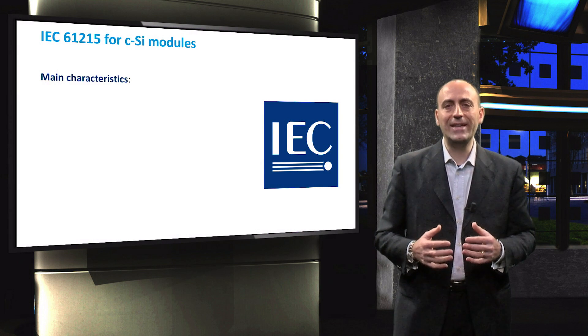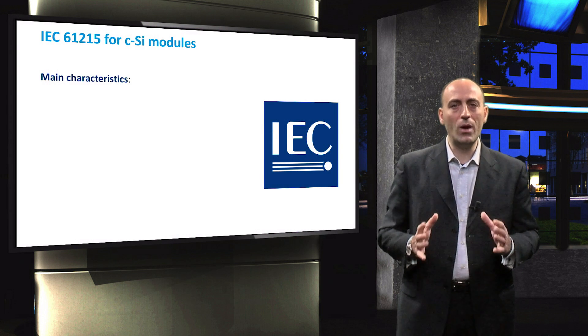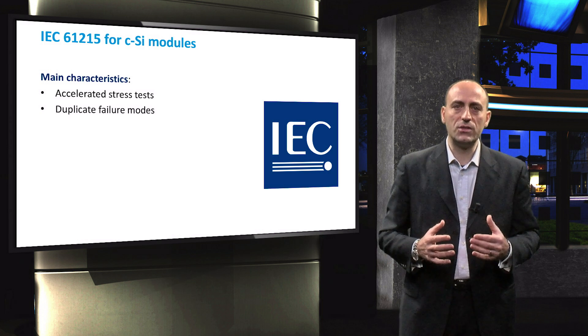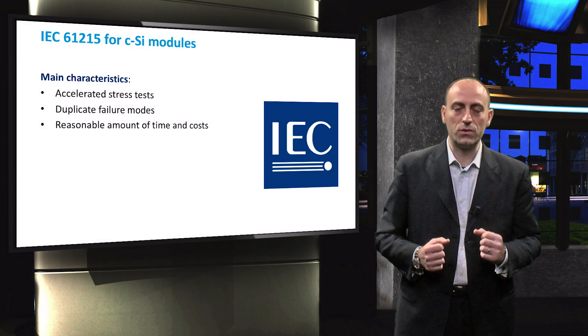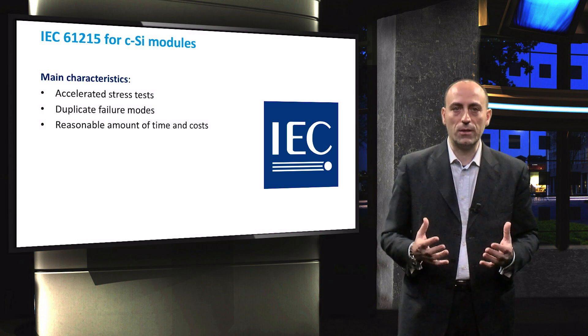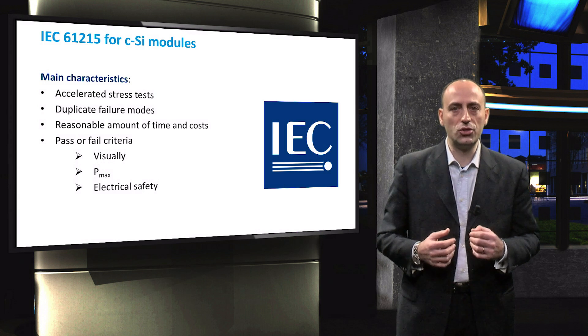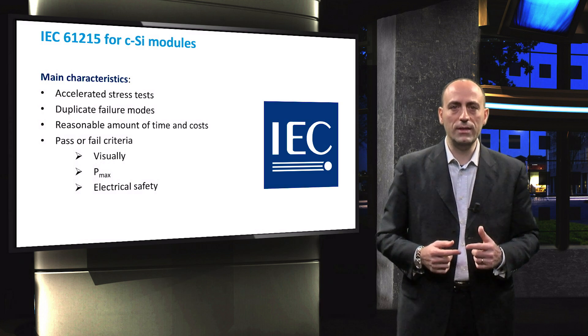Let us now focus on the IEC 61215, which is applicable to crystalline silicon modules. The qualification includes a set of well-defined accelerated stress tests that aim to duplicate failure modes observed in the field. It is important that stress levels and test durations are limited so that the tests can be completed within a reasonable amount of time and cost. The IEC 61215 prescribes a sequence of tests and criteria that have to be met after testing. There are a number of criteria that are checked visually. Also, the module's maximum power at STC is checked and compared to the value prior to the test. Furthermore, the modules should meet two electrical safety test requirements, namely the insulation test and the wet leakage current test.